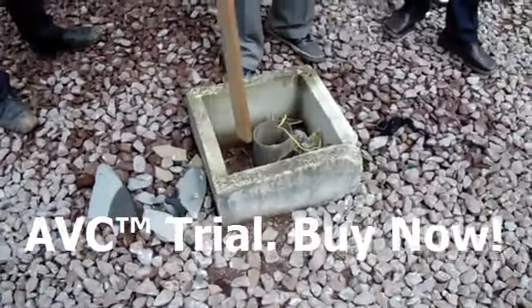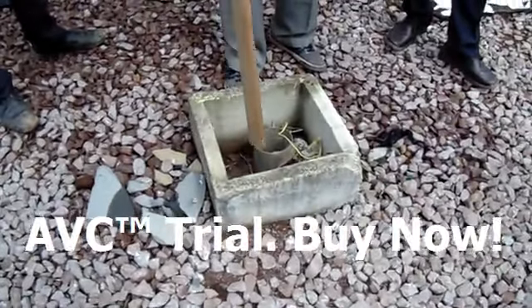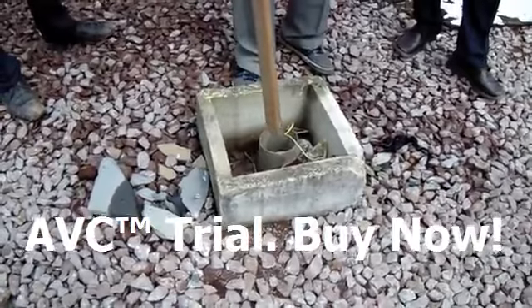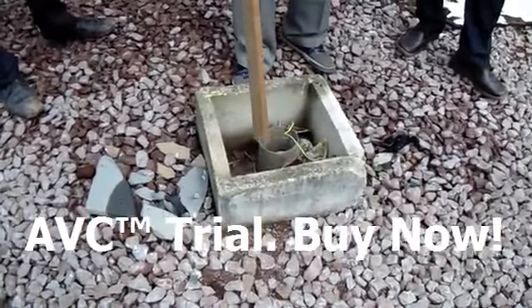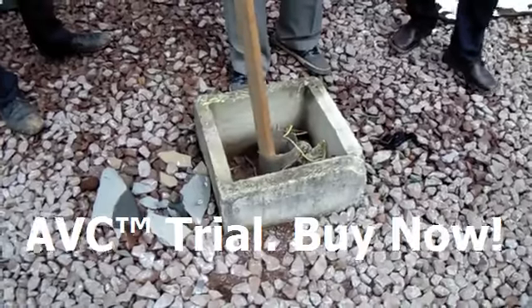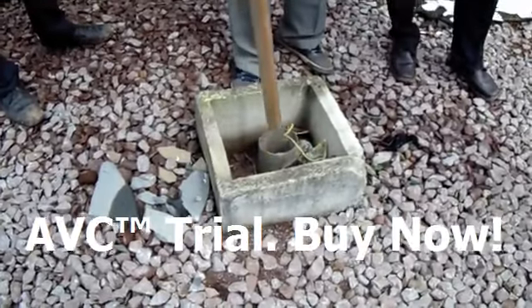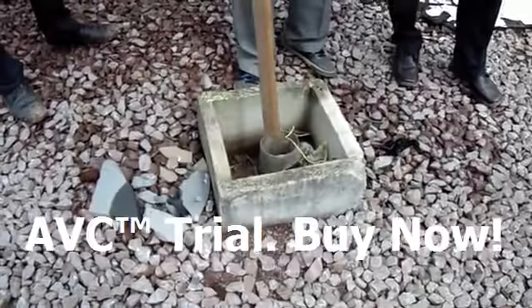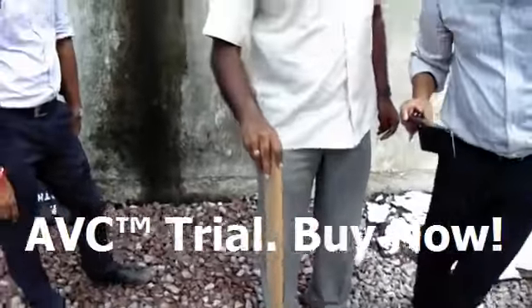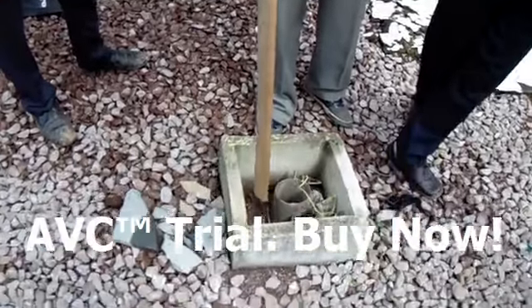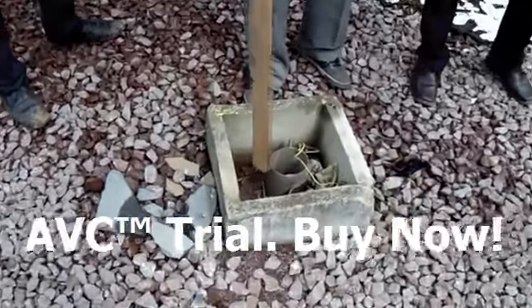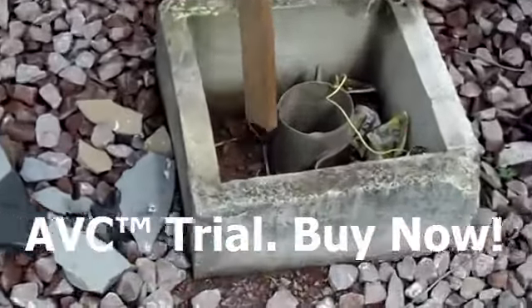After that, at regular intervals, you have to pour water only. If the earth resistance goes above 1 ohm, you have to moisten it by pouring water. Therefore, this pipe is given to pour water so that it goes down to the copper plate, which is at a depth of 3 meters from the ground level.